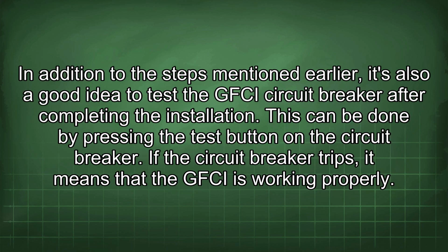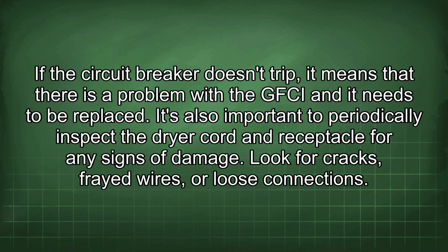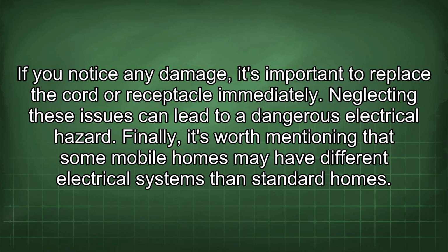In addition to the steps mentioned earlier, it's also a good idea to test the GFCI circuit breaker after completing the installation. This can be done by pressing the test button on the circuit breaker. If the circuit breaker trips, it means that the GFCI is working properly. If the circuit breaker doesn't trip, it means that there is a problem with the GFCI and it needs to be replaced. It's also important to periodically inspect the dryer cord and receptacle for any signs of damage. Look for cracks, frayed wires, or loose connections. If you notice any damage, it's important to replace the cord or receptacle immediately. Neglecting these issues can lead to a dangerous electrical hazard.